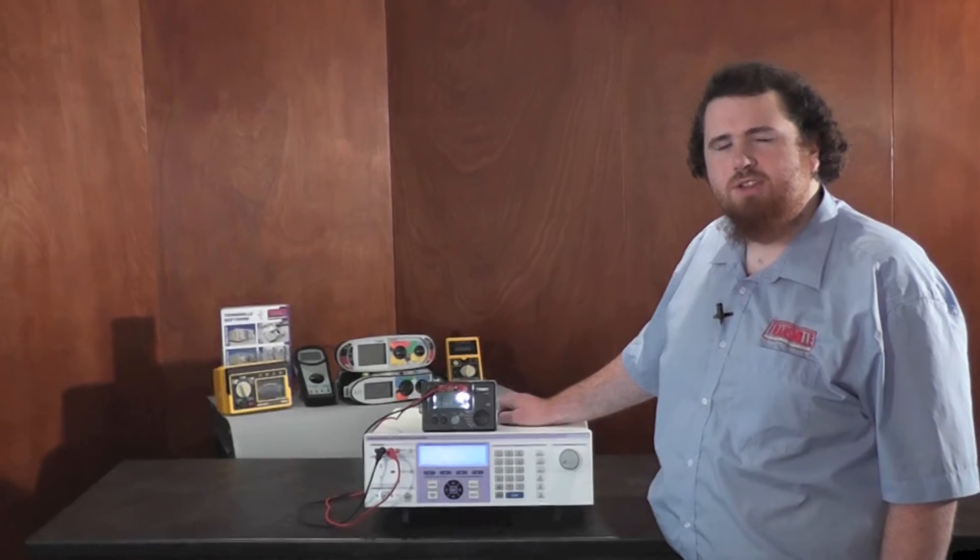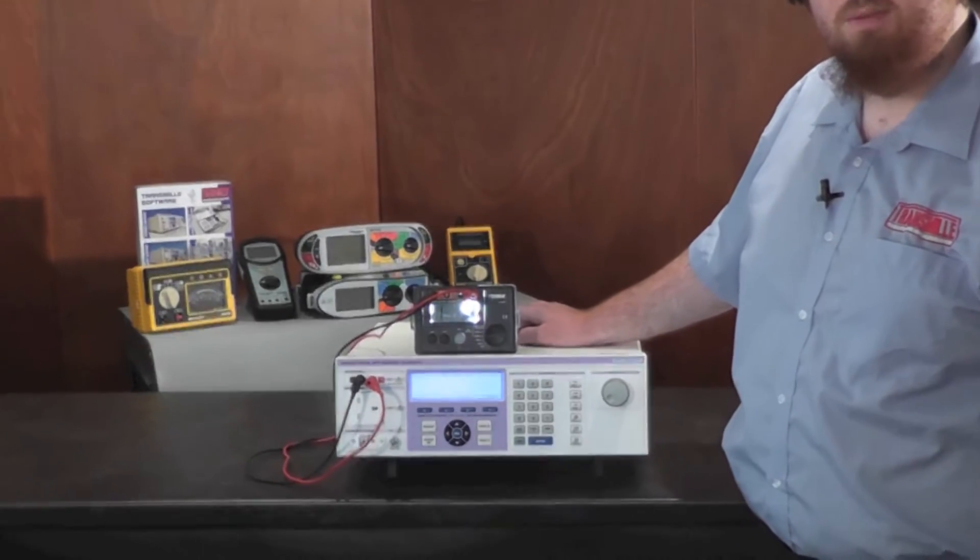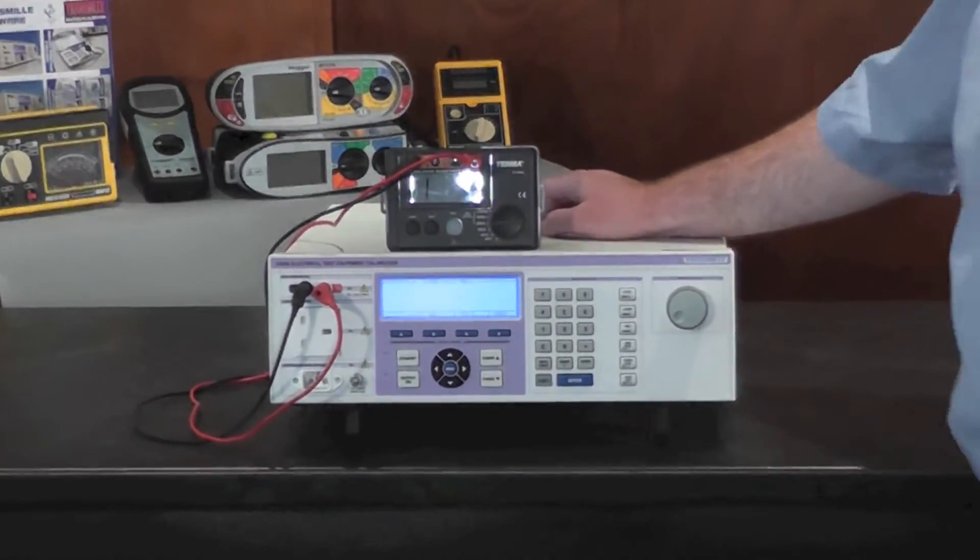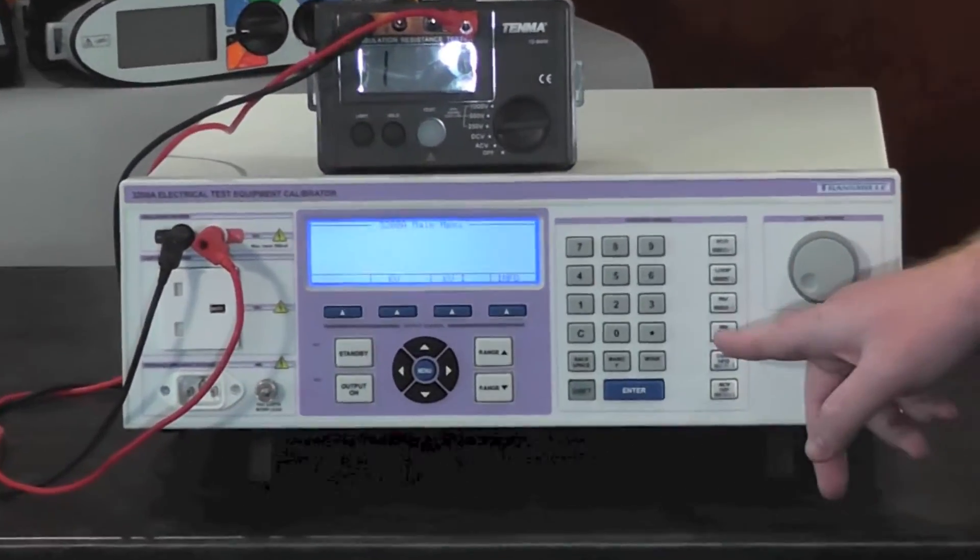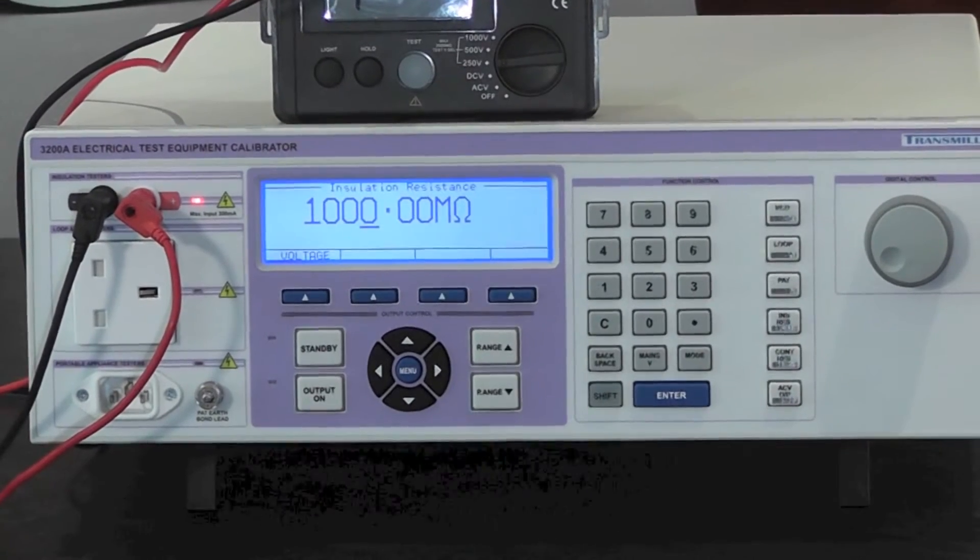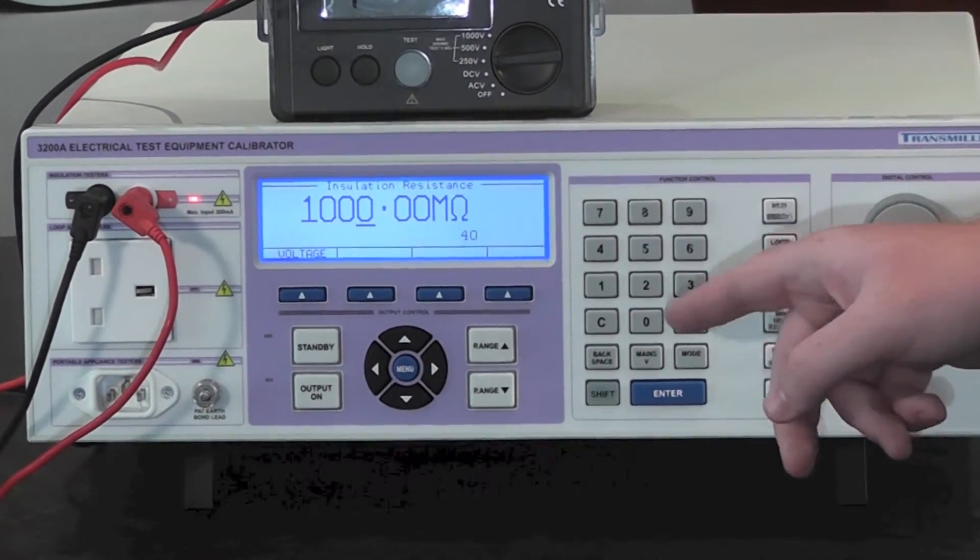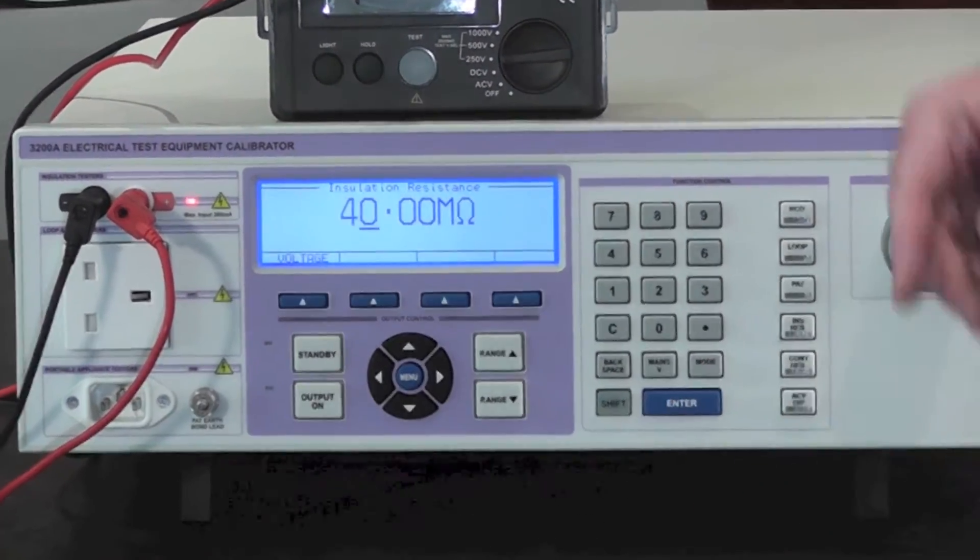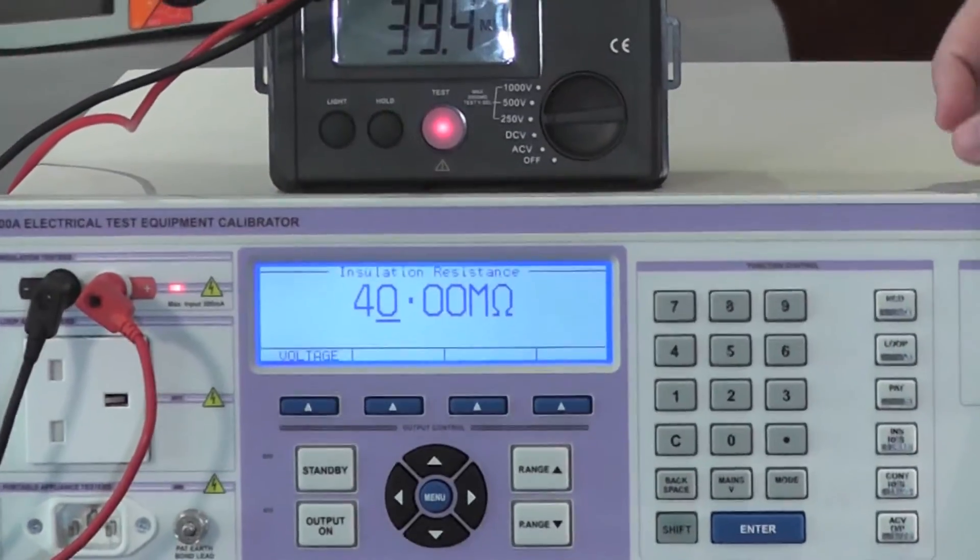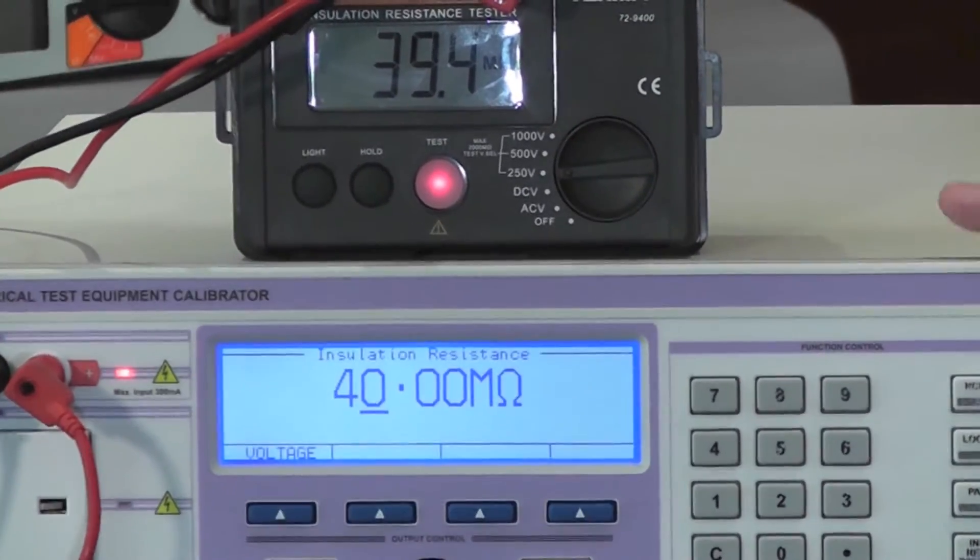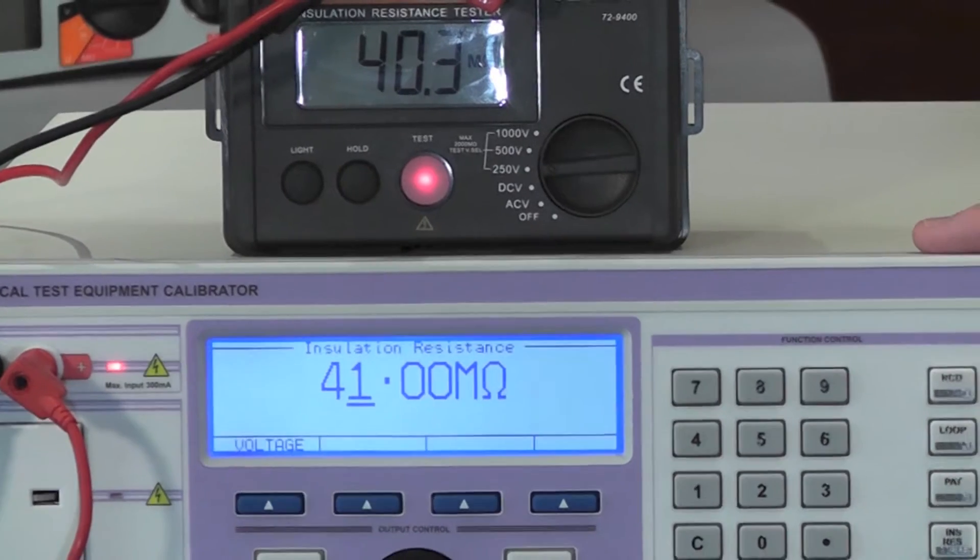Calibrating insulation testers with the 3200A couldn't be simpler. Simply select the insulation resistance function, enter the resistance required, for example 40 megaohms, and press the test button on the tester. The output resistance can be varied using the digital control.